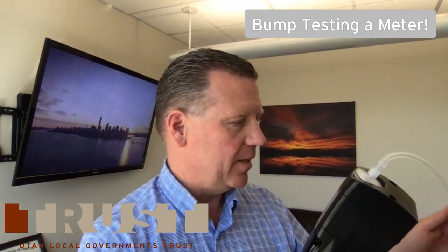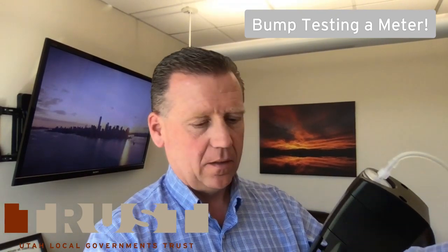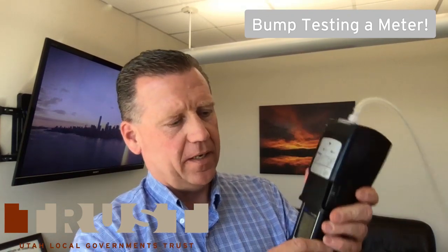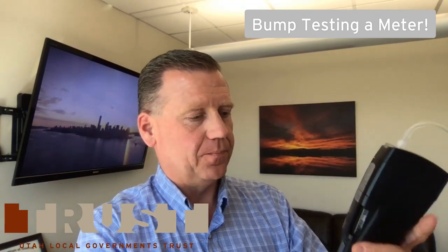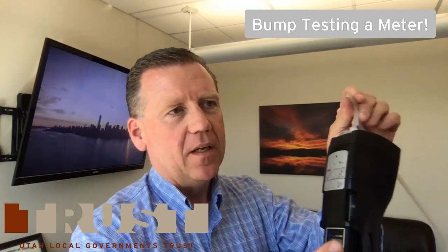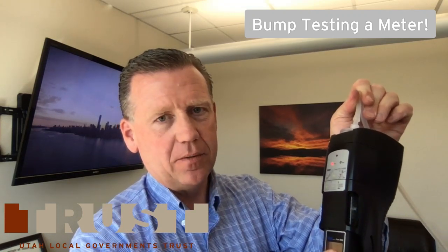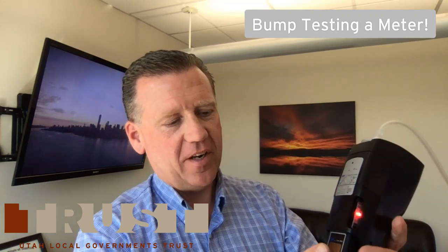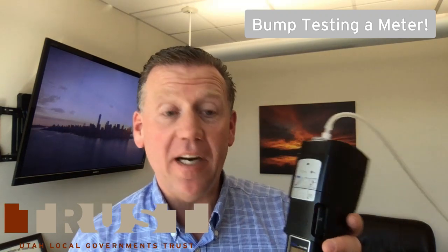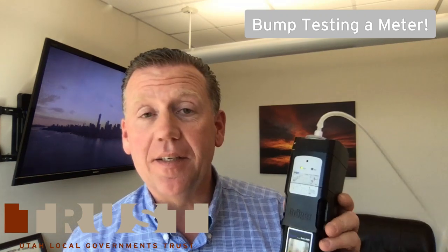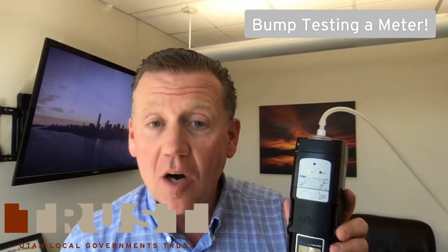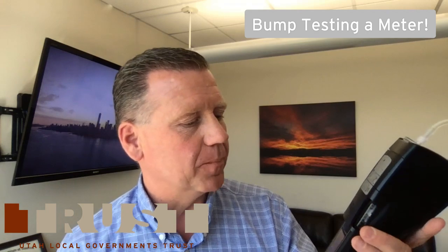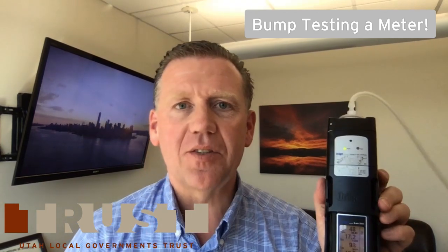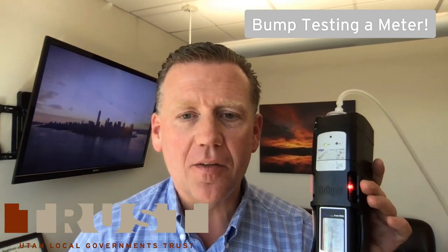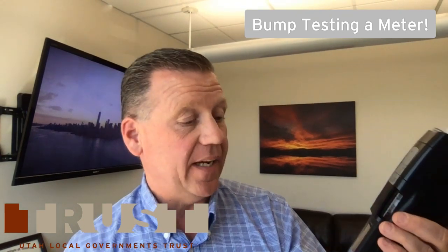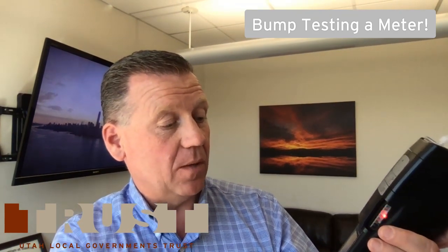So let's go ahead, and I'm going to turn on the cylinder. And it's going to get stinky in here, and I push this button, or I push this in, and it'll start flowing. With this model, I actually have to close off the flow of air, so I make sure that the alarm will work in the event that it stops flowing. Okay, now I'm going to allow this to flow for a few seconds to allow the sensors to acclimatize to that. And I definitely have some alarms going off.